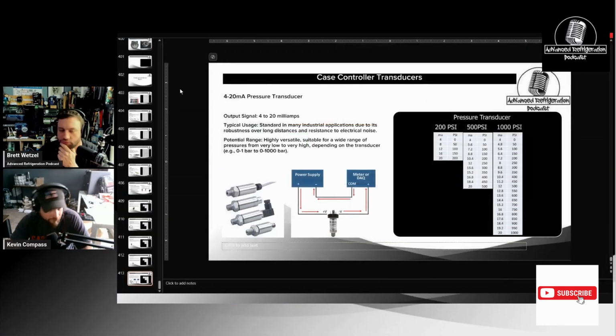Yeah, and also, if it's not reading anything, I did this in the beginning. If you put your meter leads in the wrong spots in that Fluke meter and check voltage, it'll blow the fuse inside the meter. Like a Fluke 179, if you put your meter leads on the left-hand spot instead of the right-hand, you were checking voltage, you blew the fuse in the meter. See, my one meter that does do milliamps, it is a Fluke, but it only has two leads, so it can do milliamps on either one.